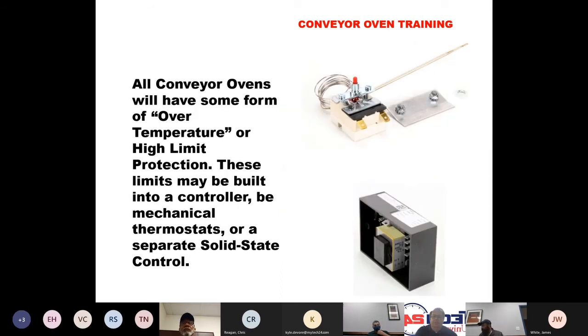All conveyor ovens are going to have some type of over temperature or high limit protection. The limits might be built into a controller. They can be mechanical thermostats, or they can be separate solid state temperature control. The solid state control at the bottom right is used by Middleby, and it will have a separate thermocouple that is sensing temperature in the cooking compartment.